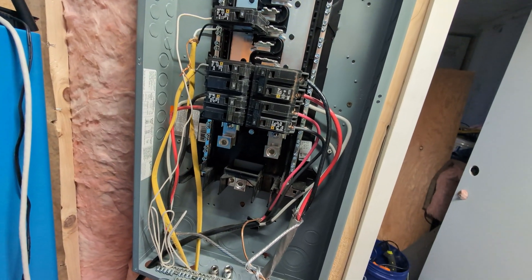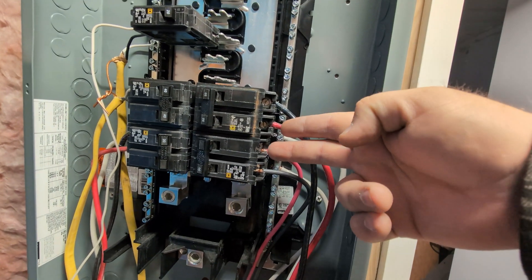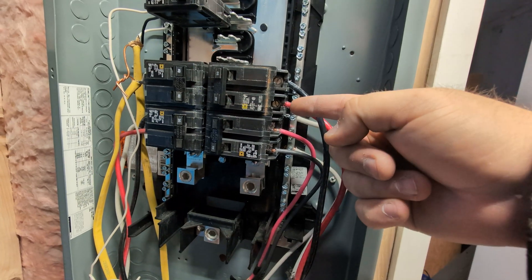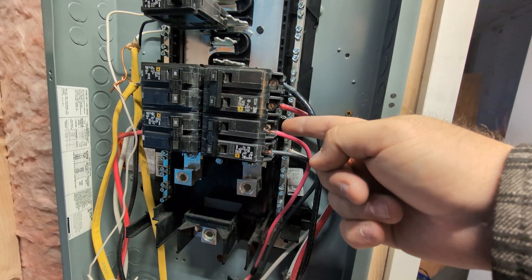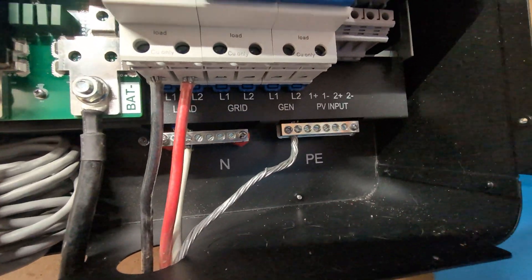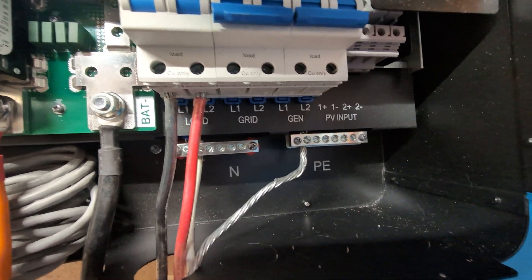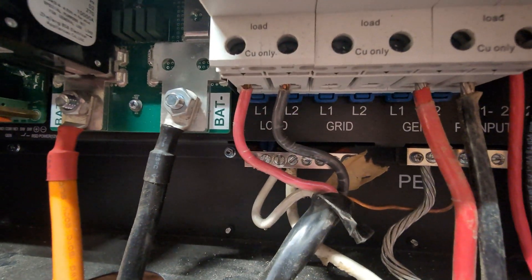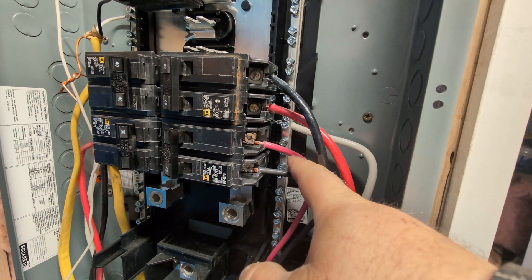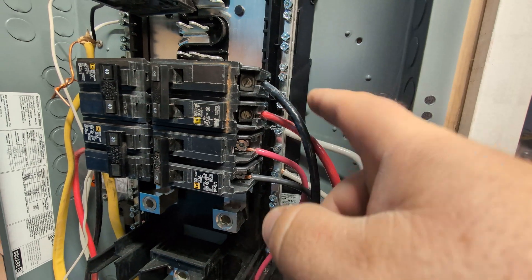To the untrained eye everything looks fine, but to the trained eye you might notice these two red lines go into opposite banks — bank one, bank two, bank one, bank two. The reason they're not tied up the same way is because they're not connected to the same output. This is the load output: L1 and L2, black for L1 and red for L2 on the top inverter. Coming down to this inverter, we've got red on L1 and black on L2.